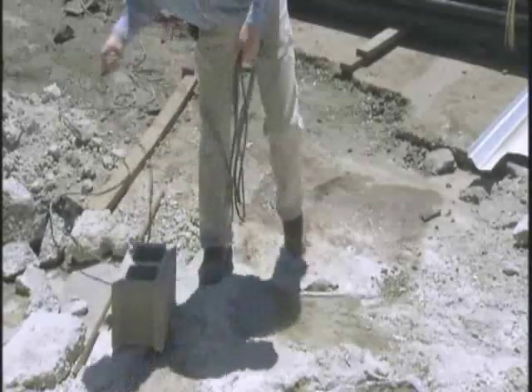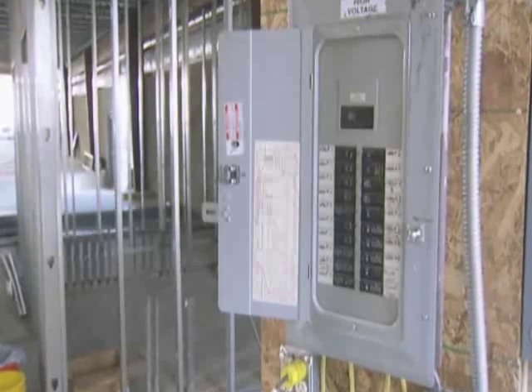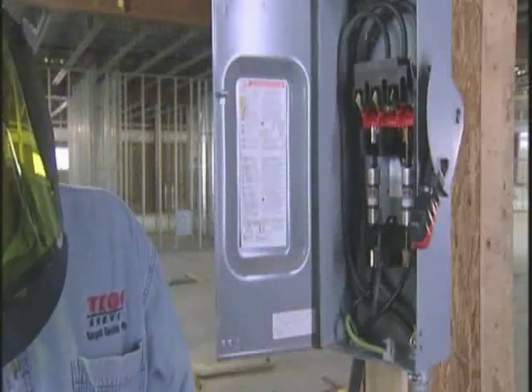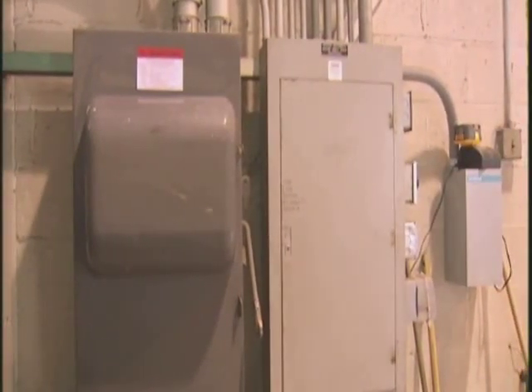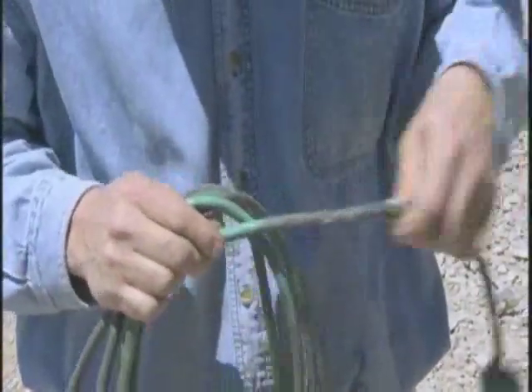Here are a few common scenarios familiar to most workers. Never allow extension cords to lay in standing water, and never run unprotected extension cords across roadways, aisleways, or walkways. Never leave energized panel boards and switches open and unguarded. Never replace a fuse with a section of copper pipe — this is an invitation to disaster. Do not pick up temporary power from an existing switch or panel source not intended for this use, and never use NM cable, 4-inch square boxes, and duplex receptacles to make extension cords — you may think you're saving time and money, but you're creating a very dangerous situation.